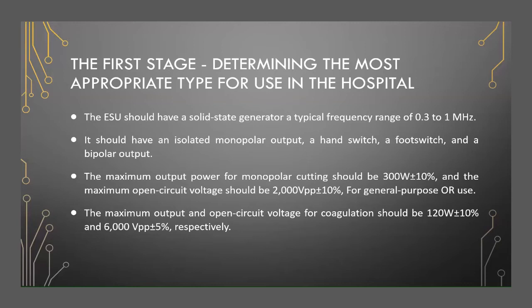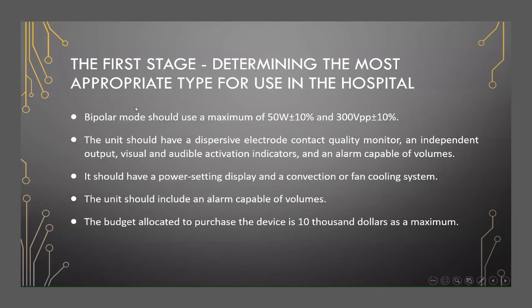For general purpose operating room use. The maximum output and open circuit voltage for coagulation should be 120 watt with a tolerance of 10% and 6,000 volt peak to peak with a tolerance of 5% respectively. Bipolar mode should use a maximum of 50 watt with a tolerance of 10% and 300 volt peak to peak with a tolerance of 10%.